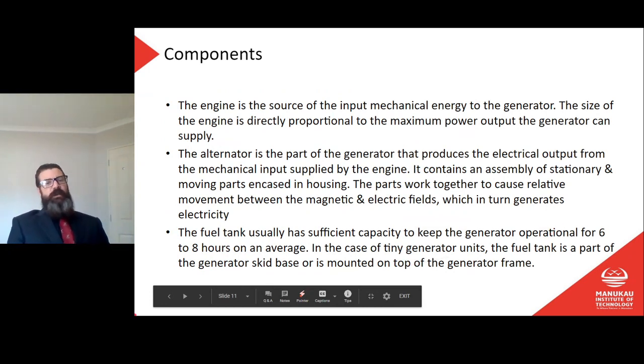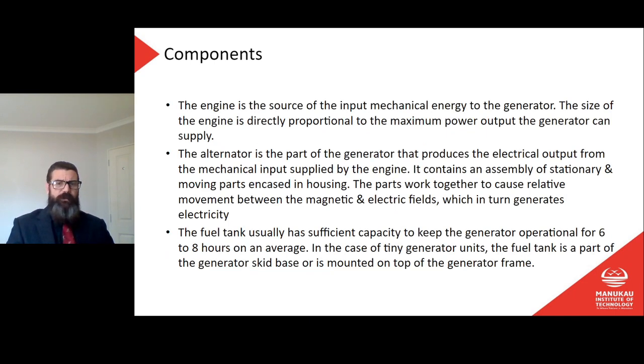Alright, so the energy, the components: the engine is the source of the input mechanical energy to the generator. We know about this. The size of the engine is directly proportional to the maximum power output that the generator can supply. Well, that makes sense, right? If I want more power, I need a bigger engine. The alternator is part of the generator that produces the electrical output from the mechanical input supplied by the engine. It contains an assembly of stationary and moving parts encased in a housing. The parts work together to cause relative movement between the magnetic and electric fields, which in turn generates electricity. A fuel tank usually has sufficient capacity to keep the generator operational for 6 to 8 hours on average. In the case of a tiny generator unit, the fuel tank is part of the generator skid base or is mounted on top of the generator frame.